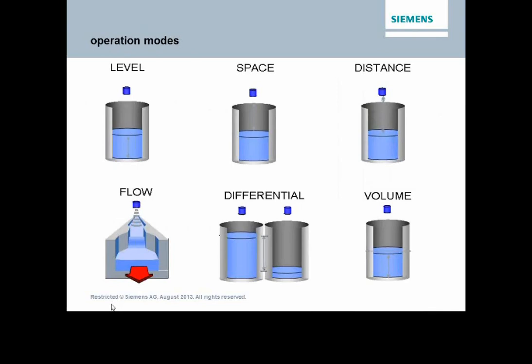When it comes to operation modes, the main thing we're going to look at here are the top three. Level, which is simply our 0 calibration point up to a given material surface. We call that level, and all of the devices that use time of flight get that measurement indirectly.